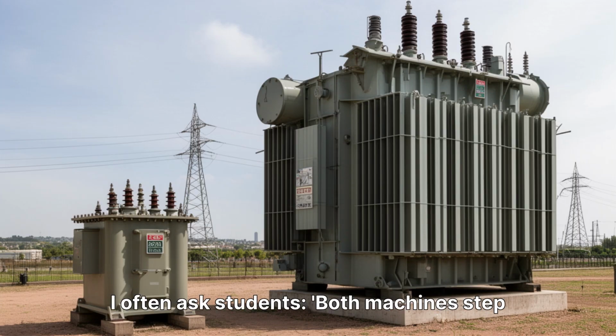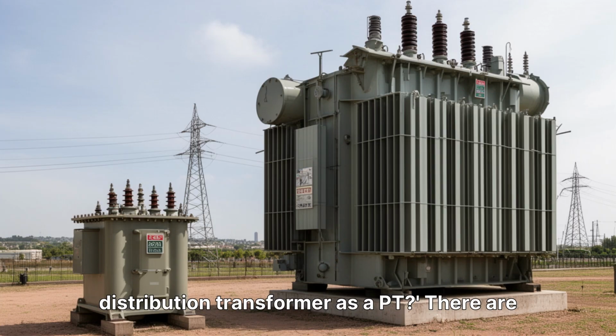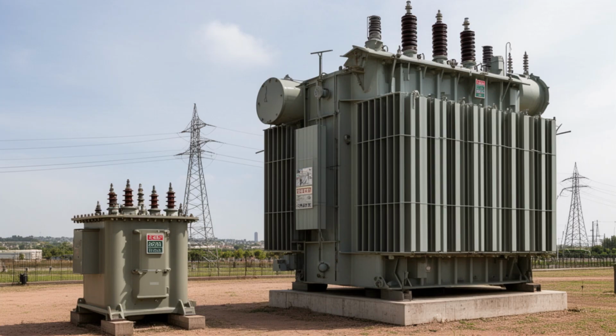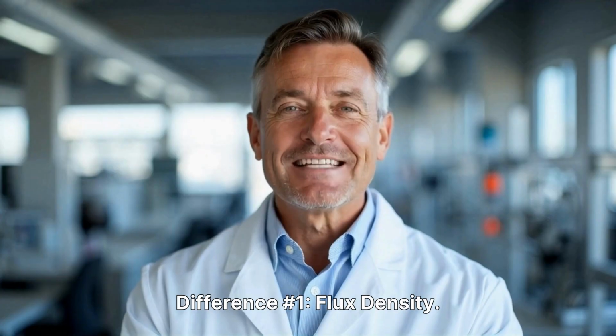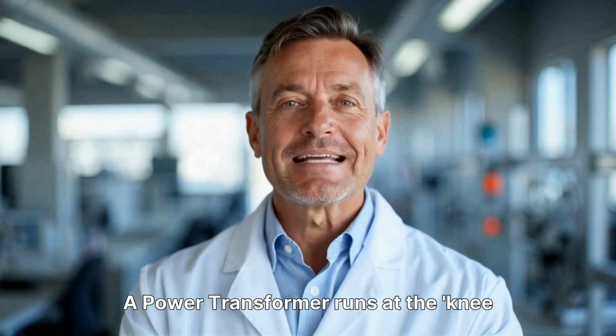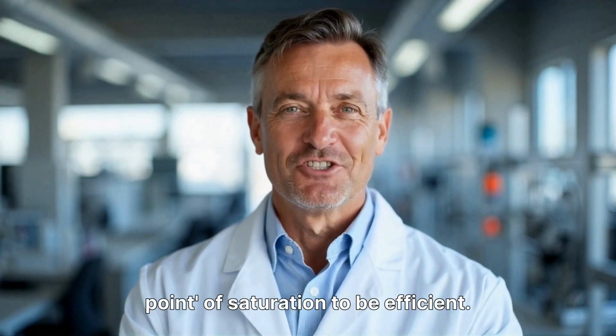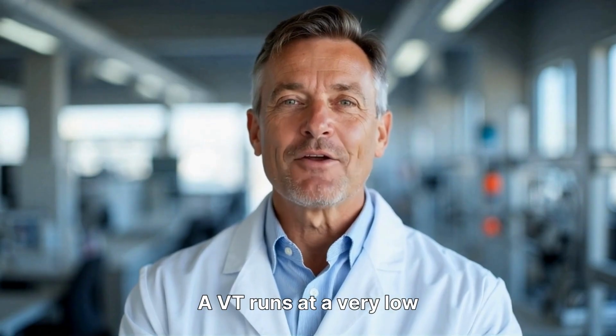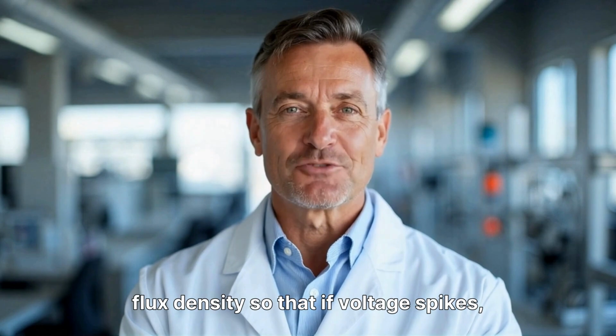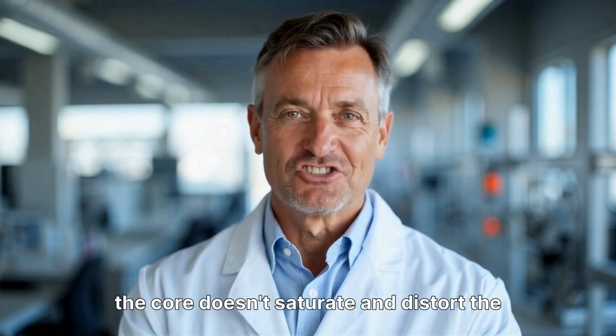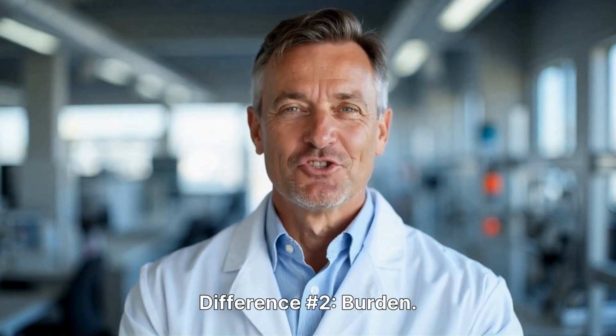I often ask students, both machines step down voltage. Why can't I just use a small distribution transformer as a PT? There are three critical engineering differences. Difference number one, flux density. A power transformer runs at the knee point of saturation to be efficient. A VT runs at a very low flux density so that if voltage spikes, the core doesn't saturate and distort the output.